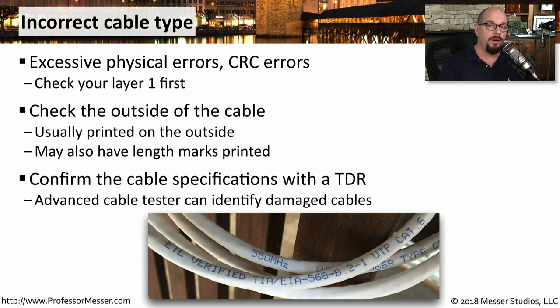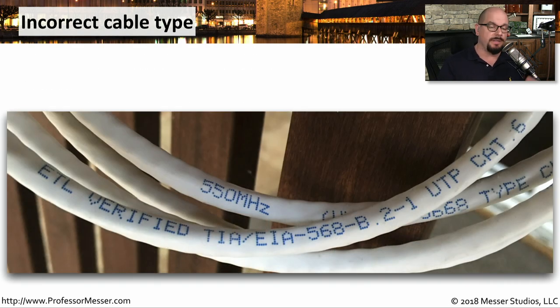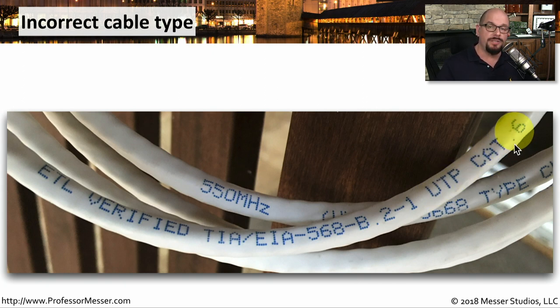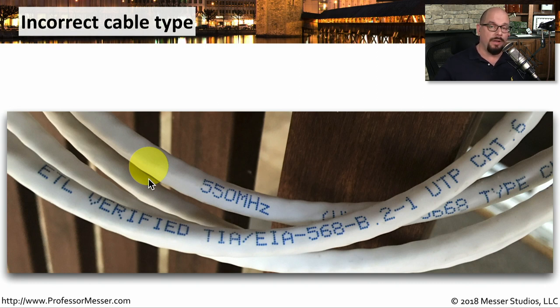Here's a larger picture of the outside of a cable from the studio. You can see this one is rated for 550 megahertz, which makes it at least a category 6 cable. Looking at the outside, it says ETL verified TIA EIA 568B standard. It is a UTP or unshielded twisted pair cable, and it is a category 6 rated cable. Some cables even have length markers on them, so you can look at a cable going into a wall and the cable coming out on the other side to see the difference in lengths — in those cases, you wouldn't have to measure manually or get a TDR.